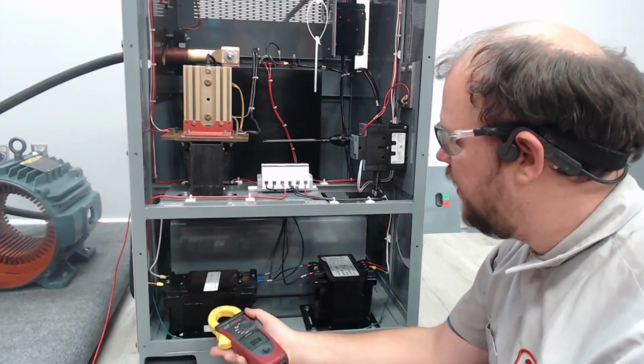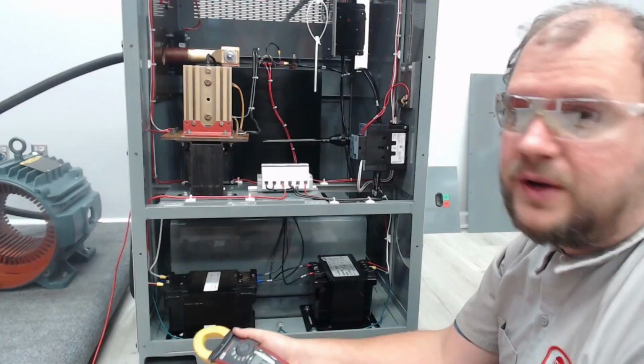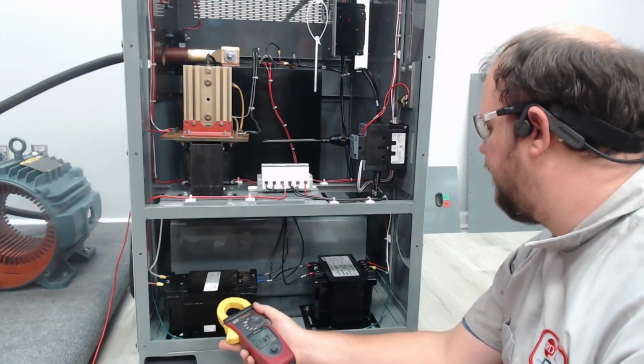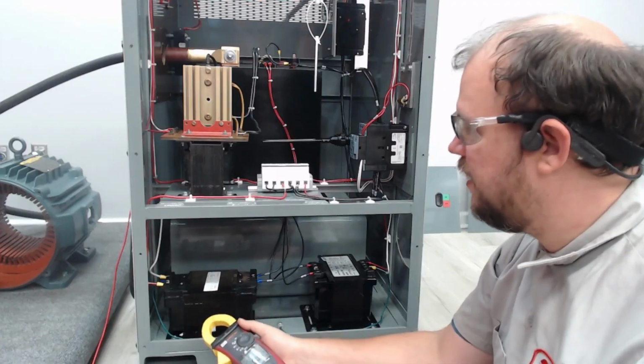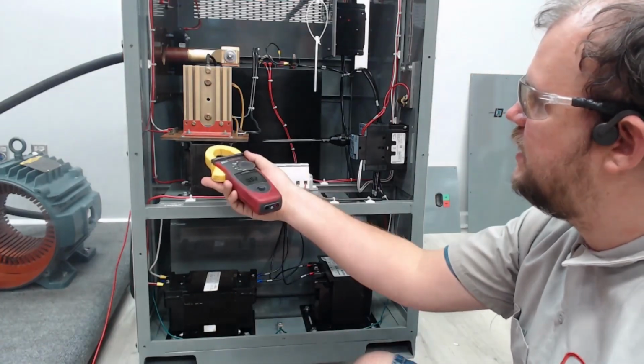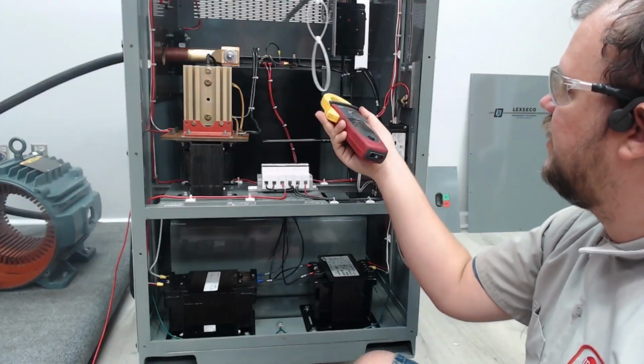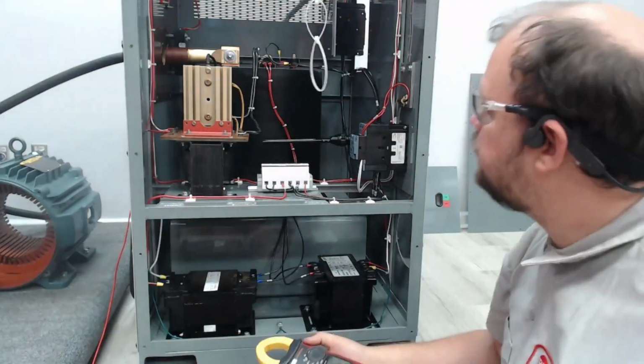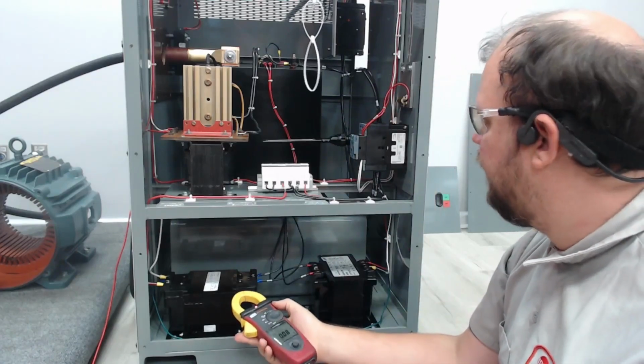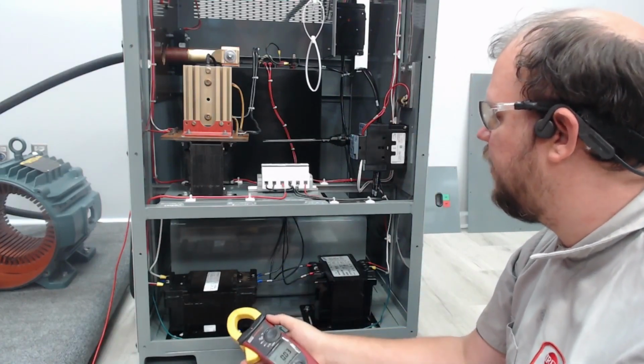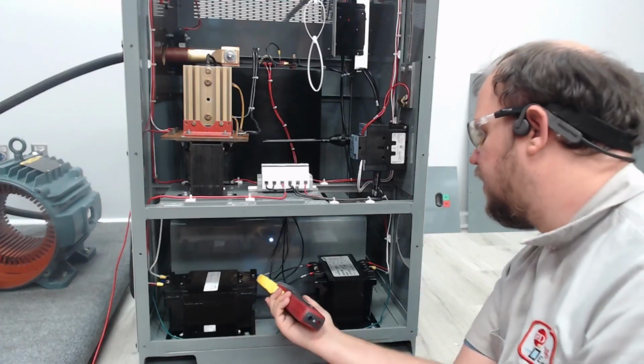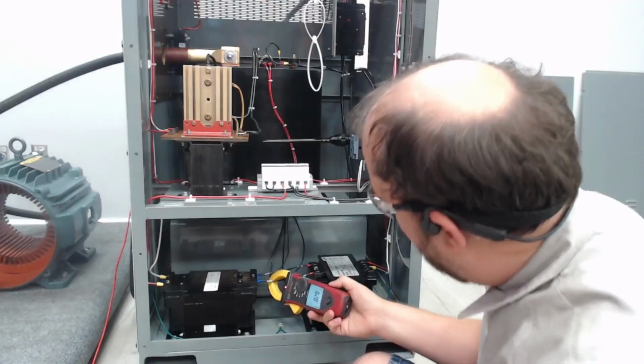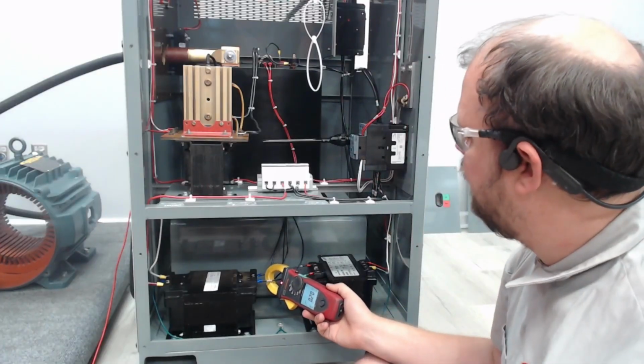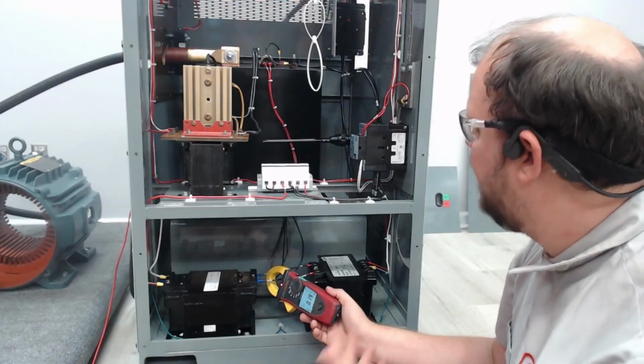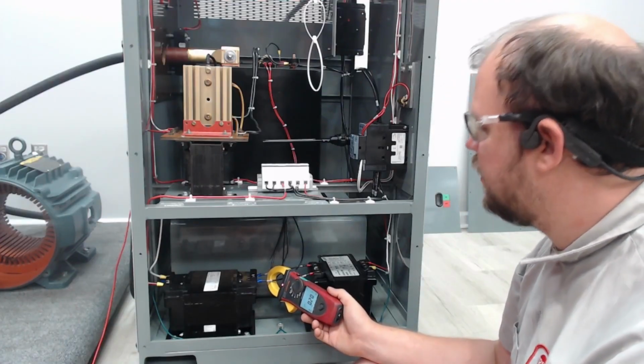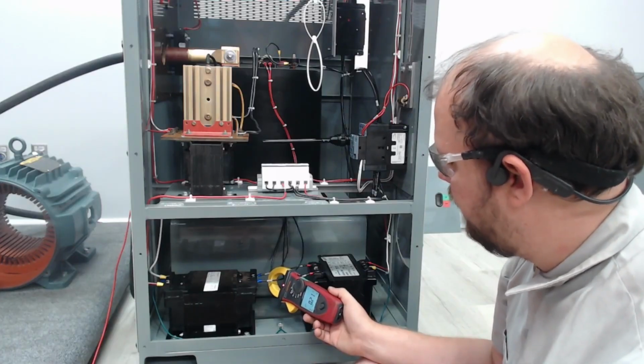Okay, now the bigger transformer on this one, it's a 1.5, could be a 3, could be a 2. Doesn't matter. It's bigger than a 500 VA transformer. So it's going to be the big one. That's the one that's actually powering your DC supply, which does the controls of the VRT and allows it to pull main power from the wall. If you're tripping, it's probably going to be this transformer because it's the one that actually has a load on it. So at no load, we're at 0.2 amps. 0.2 amps without anything on, so that's what we're drawing. I think the fuse for this unit is a 2 amp fuse, so obviously we're way in the clear for that.